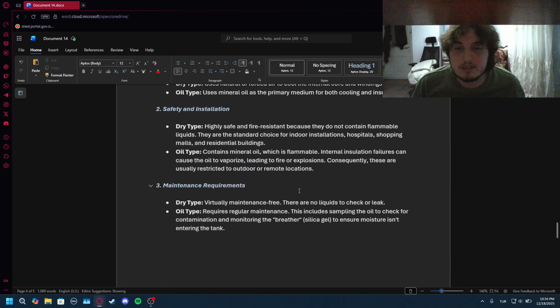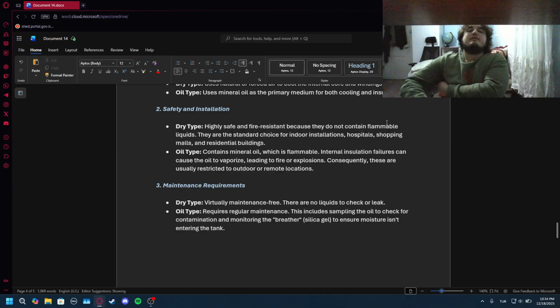Maintenance requirements: dry type, virtually maintenance free. There are no liquids to check or leak. You just check if the values are correct, and if the transformer is hot or not, then that's it.